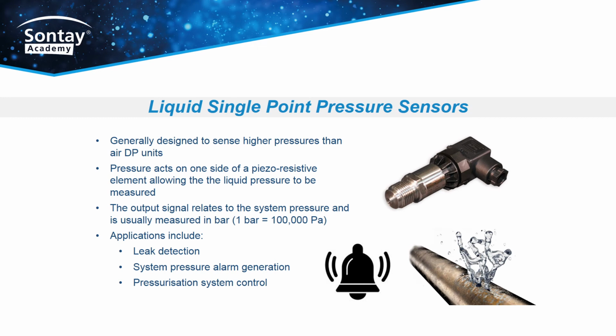Liquid single-point pressure sensors. These are generally designed to sense higher pressures than air DP units. Pressure acts on one side of a piezo-resistive element, allowing the liquid pressure to be measured. The output signal relates to the system pressure and is usually measured in bar. 1 bar equals 100,000 pascals. Applications include leak detection, system pressure alarm generation, pressurization and system control.